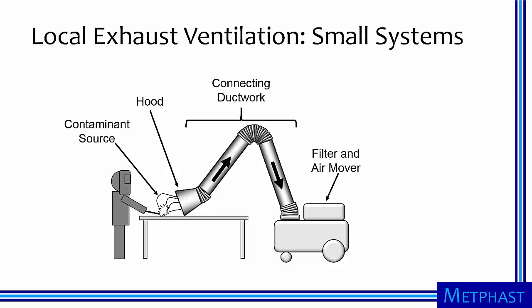Air from a local exhaust ventilation system can be cleaned and then recirculated back into the facility, but this practice should be restricted to contaminants of low toxicity. Air is moved through the system by a large industrial fan. Local exhaust ventilation systems can also be small and self-contained. They have the same components as the larger system: a hood designed to evacuate the contaminant, connecting ductwork to move the contaminant to an air cleaner, and finally the air cleaner and an air mover. In this case, the filter and air mover are contained in a single housing.